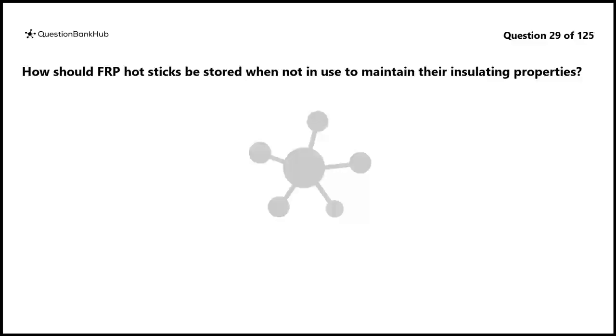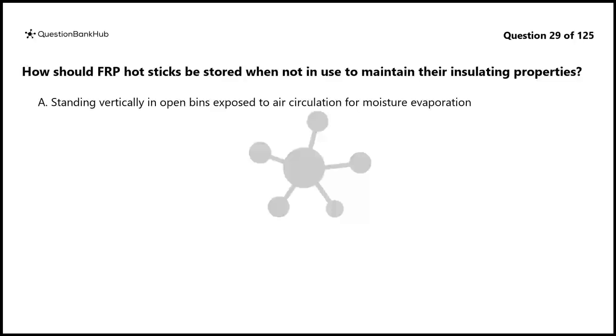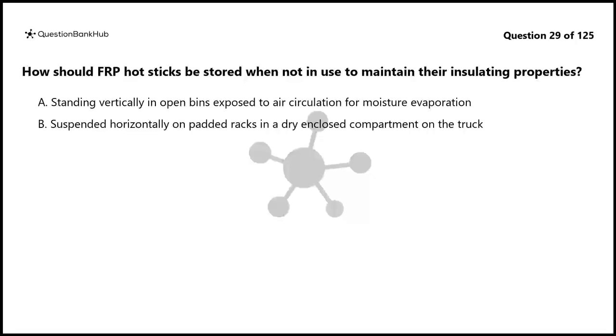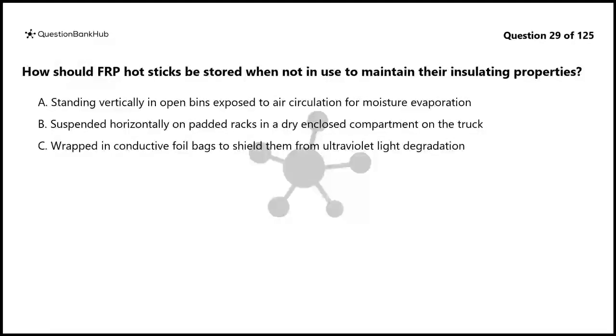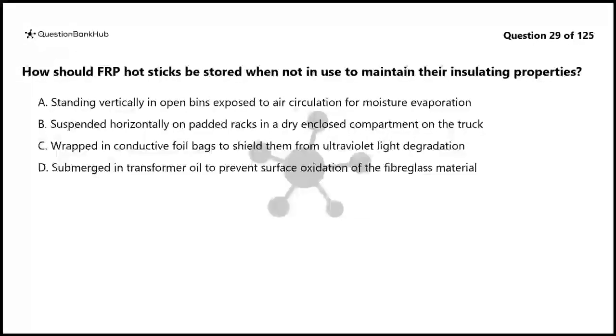Question 29. How should FRP hot sticks be stored when not in use to maintain their insulating properties? A. Standing vertically in open bins exposed to air circulation for moisture evaporation. B. Suspended horizontally on padded racks in a dry enclosed compartment on the truck. C. Wrapped in conductive foil bags to shield them from ultraviolet light degradation. D. Submerged in transformer oil to prevent surface oxidation of the fiberglass material.